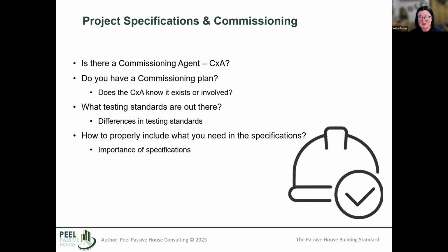Part of that is the commissioning plan, the plan of attack for making sure that everything is sealed properly and measured properly, and that testing and balancing is done correctly. We've had projects where multiple suites were sealed off while they measured one suite, and we didn't know if the system would be able to work when everything was open. So make sure that whoever is doing your testing and balancing really understands that it has to be done as though it's an operation, and not just isolating certain things.